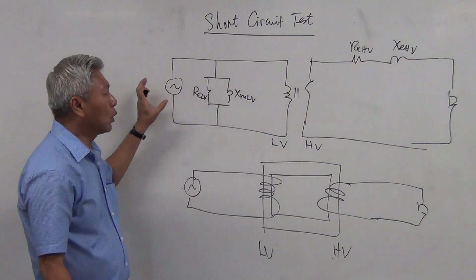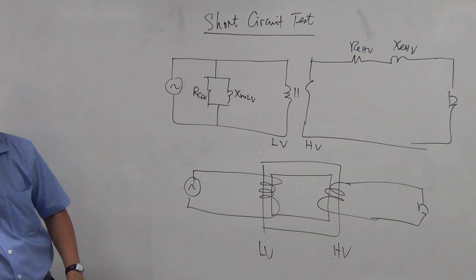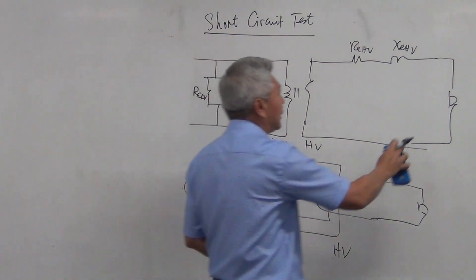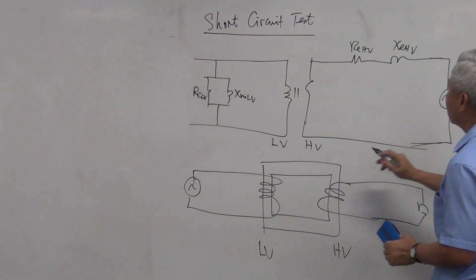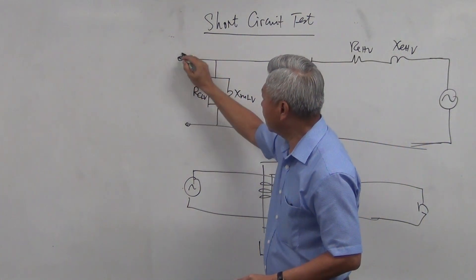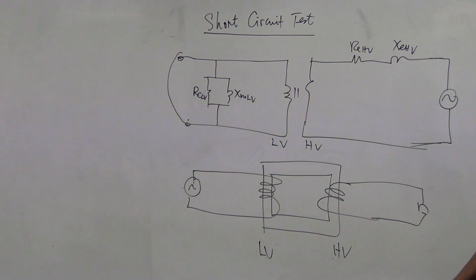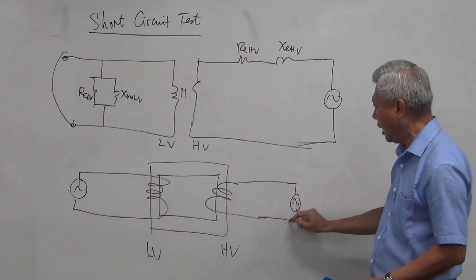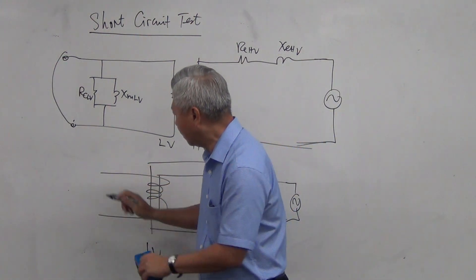The open circuit test experiment was done on the low voltage side. The short circuit test is the opposite — we do the experiment on the high voltage side. We remove the load, connect the power supply to the high voltage side, and the low voltage side is short-circuited. That's how the name comes about: short circuit test.